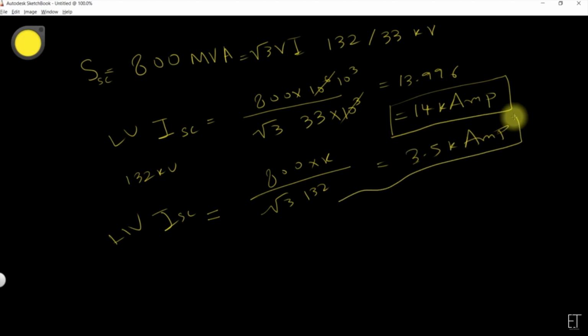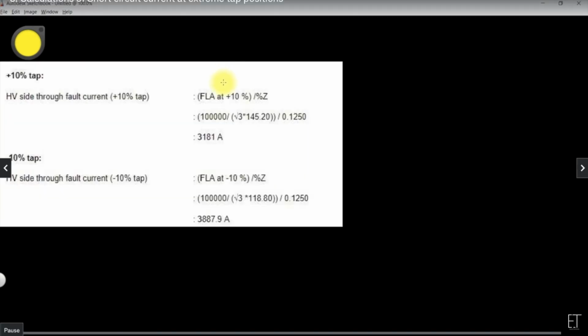So in this way, you have now calculated the fault current in case of HV fault and LV fault, and you have now understood the relationship between the percentage impedance, the fault MVA and the fault current. This is the basic formula to do the calculation. When we are doing our setting calculations, we will obviously be using this formula. Thank you very much.